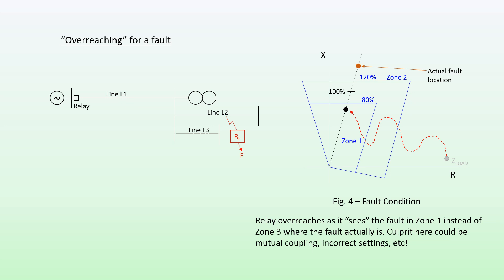Now do note: suppose the fault was within the Zone 1 reach, but due to fault resistance the apparent impedance has moved out to a position further away. The relay still sees the fault further than it actually is, so technically we can say the relay has under-reached. However, from a system point of view, the relay will still operate within Zone 1 time and still operate correctly.